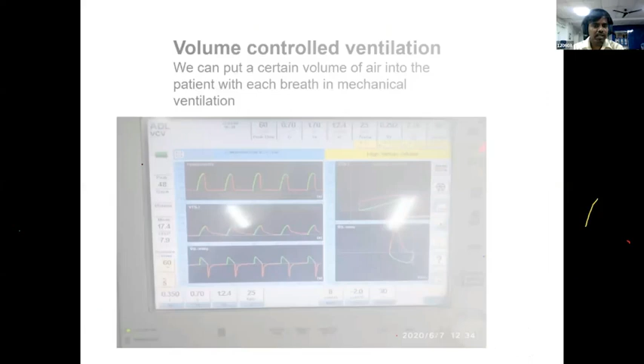Yes. So in VCV mode, I have the same ventilator settings, and why? Because you should know the peak. If the peak is increased, what will you do? You do suctioning. Number one, you have to observe the plateau pressure. Here is the inspiratory pause. When inspiration starts, you have to press this, inspiratory pause, so the plateau pressure will come. Understood? So plateau pressure should never go high.